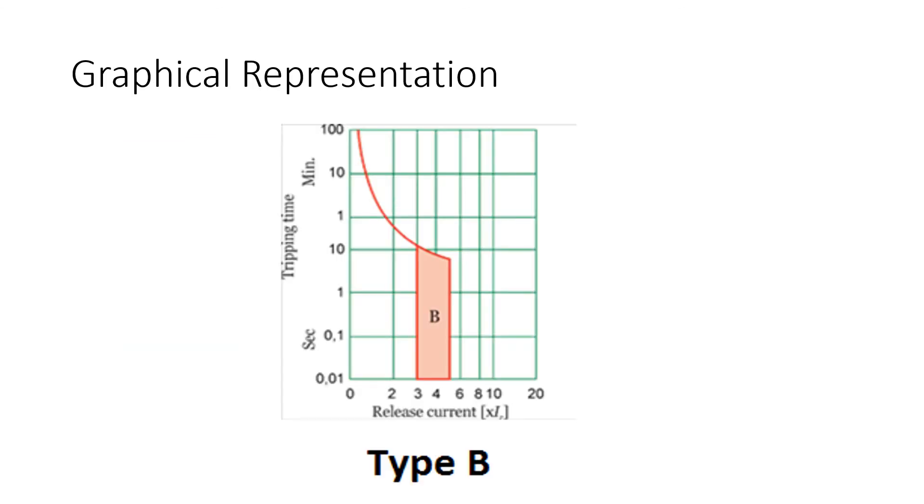After plotting the graph you will find such type of nature inverse characteristic and that is of type B in which it operates if your rated value varies from 3 times to that of 5 times. This is how MCB testing is carried out.